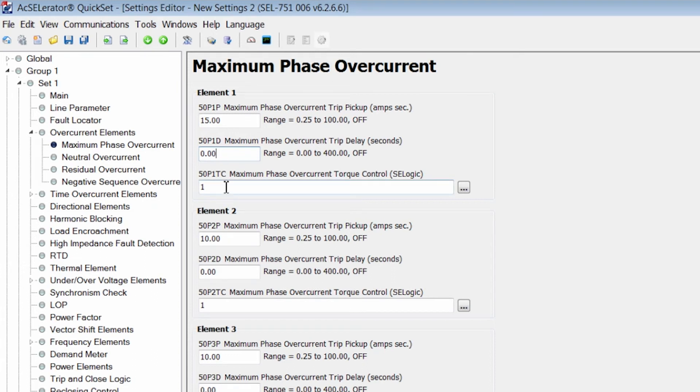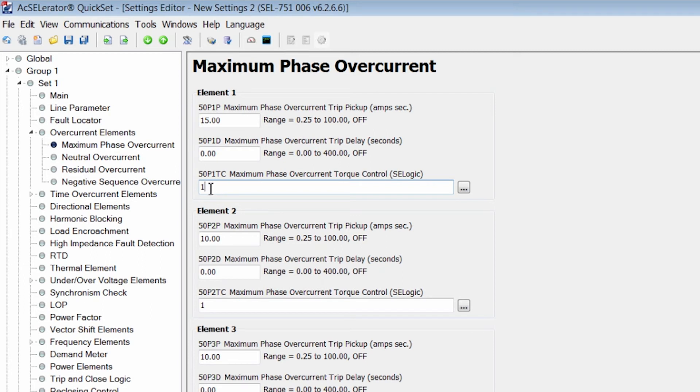The 50P1TC is the torque control that can block the operation of the 50 element. For our case we're going to set it to one to continuously have it active. These are essentially the settings you need to consider for setting an overcurrent element.